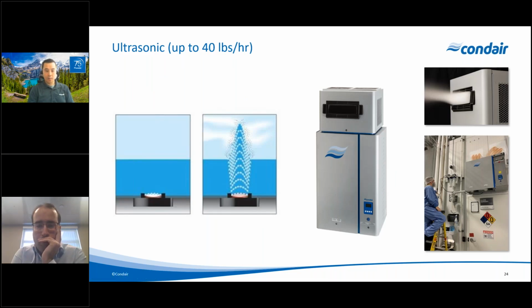The next technology that we'll look at here is a smaller capacity in-space system, and it's our US series or ultrasonic humidifier. So the way that this works is we have inside of that cabinet a series of piezoelectric transducers that vibrate at an ultrasonic frequency. So those work by breaking the surface tension of the water and generating a really, really fine mist.